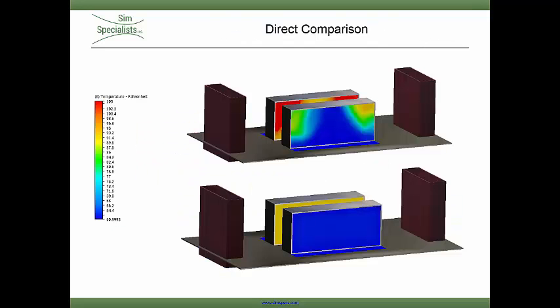Further investigating the model, we see that the temperatures are significantly lower in the second design with the hot aisle containment.